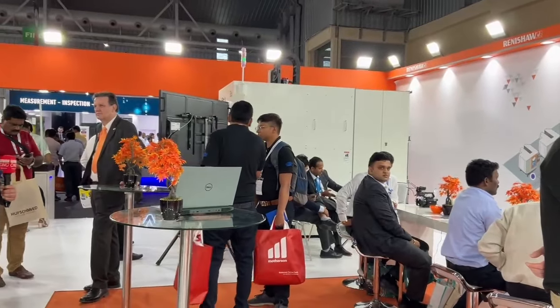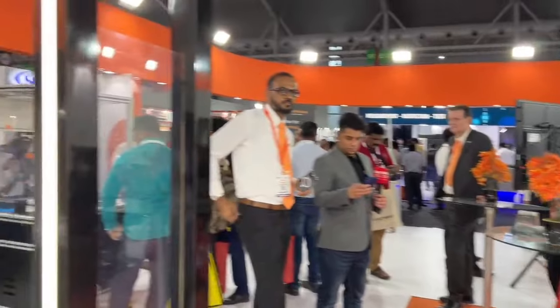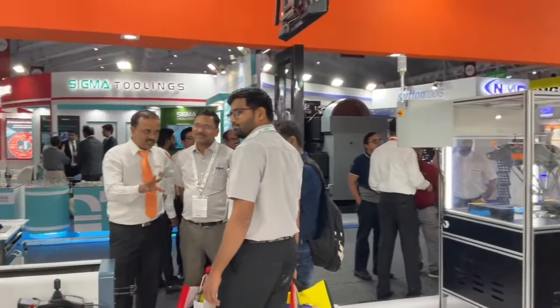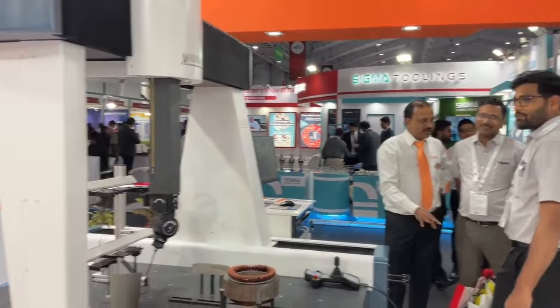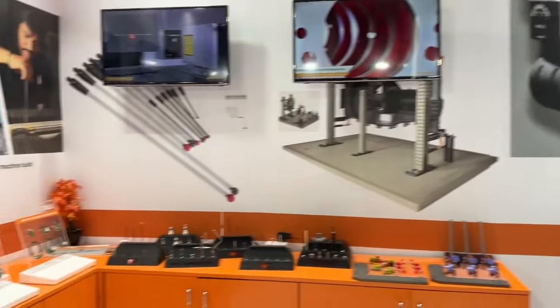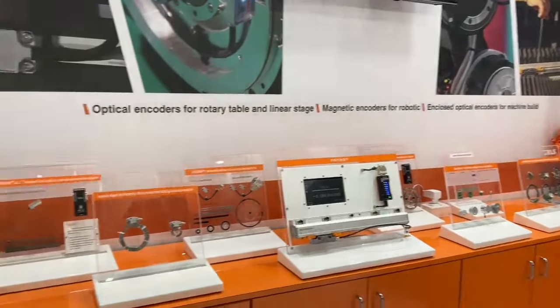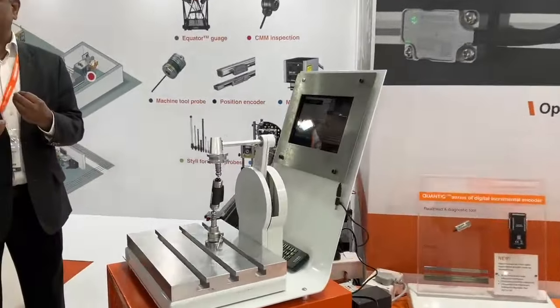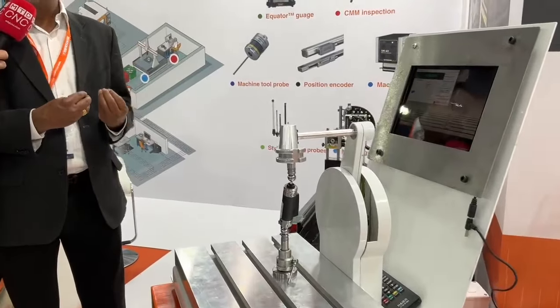There are multiple other usages too. You can use the ball bar to identify how good your machines are. You may have machines of different ages, 5 years, 10 years, 2 years, 1 year. You might have a perception that a 5 year old machine may not give good accuracy while a 1 year old machine would, but your perception could change if you run a ball bar test. You might see exactly the opposite result.